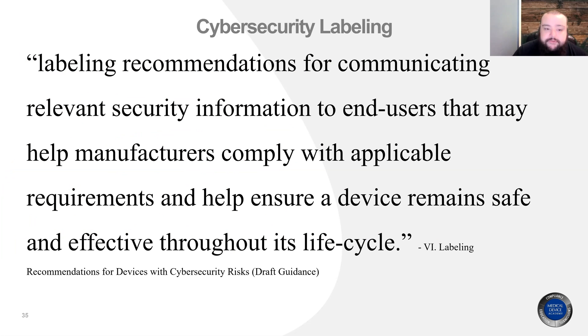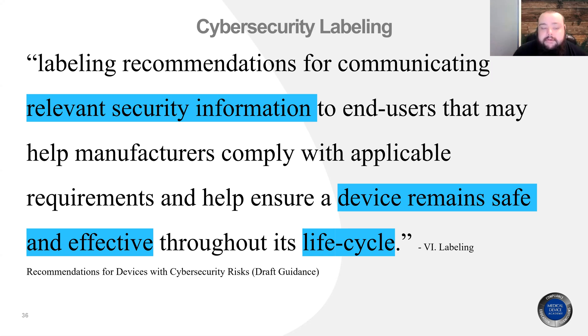This is a quote taken from the draft guidance — not for implementation, only a non-binding recommendation. Your labeling for your 510K is something that will communicate relevant security information to your end users, whether that's patients or healthcare providers. The purpose is to help manufacturers ensure that your device remains safe and effective through its entire product lifecycle — not just during development and not just during the post-market phase, but from start to finish.